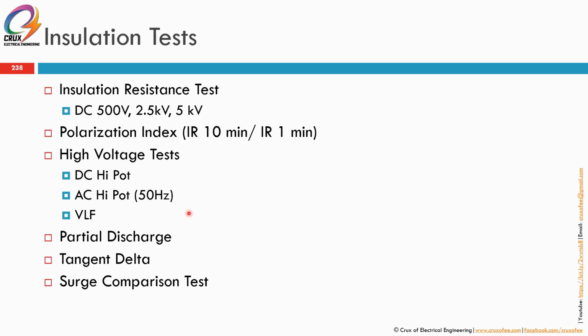Okay, then we have the insulation test, which is the IR test: DC 500 volt, 2.5 kV, 5 kV. Even now we have IR test up to 10 kV and 15 kV. So typically we will only do up to 5 kV. 500 volt is for low voltage, 2.5 kV is for up to 4.6 kV rated equipment. This is based on Petronas technical standard, and 5 kV is for anything above 4.6 kV voltage rated equipment.